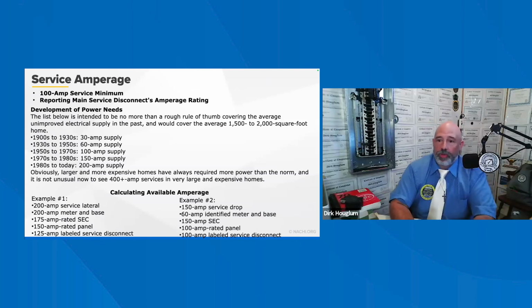Now, for houses serving one family, the electricity should be 100 amp. We talked about that. According to the home inspector's standard of practice, the inspector shall describe the main service disconnect. We've talked about that. Older homes may not have enough power for a modern family. Second, many insurance companies will not insure a property with less than 100 amps. So kind of keep that in mind.